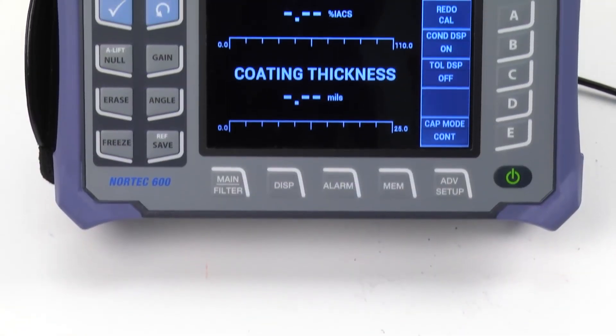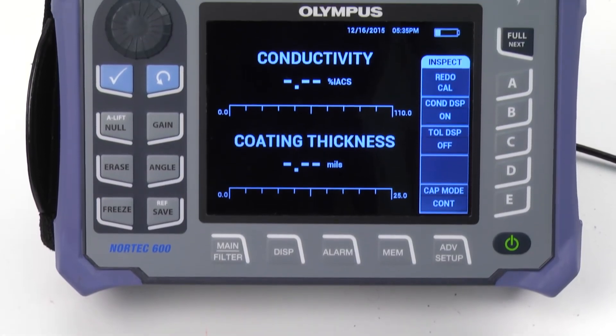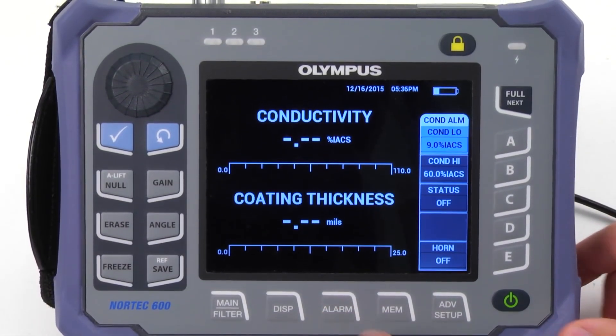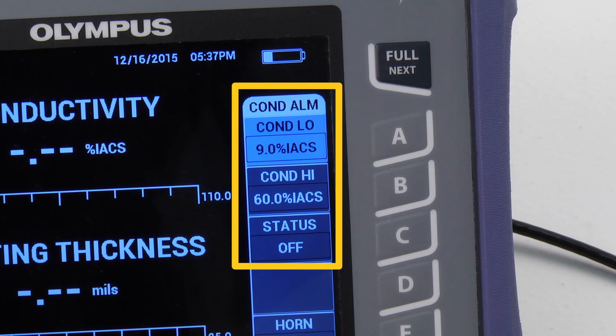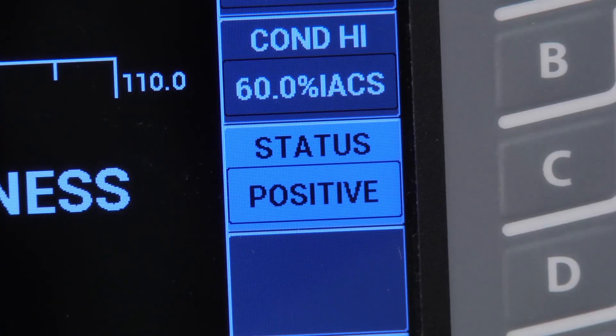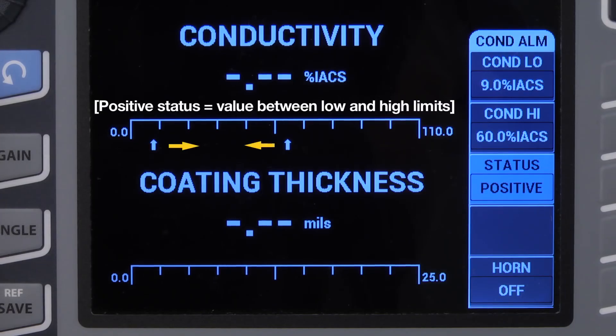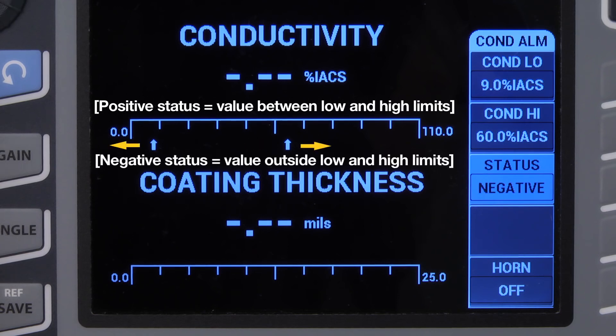It is possible to add alarms to both scales. To do so, press the alarm key. The first alarm is meant for the conductivity scale. You can set the lower limit using A and the upper limit using B. You can adjust the status if you want the alarm to be positive or negative. A positive status means the value is between the low and high limits; a negative status means the value is outside the low and high limits.